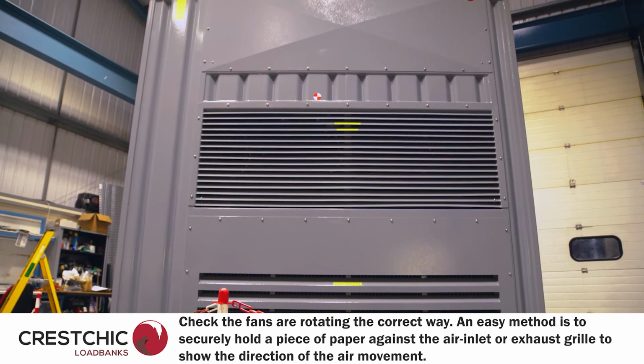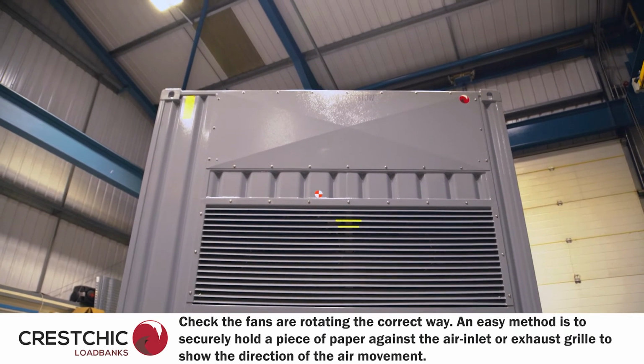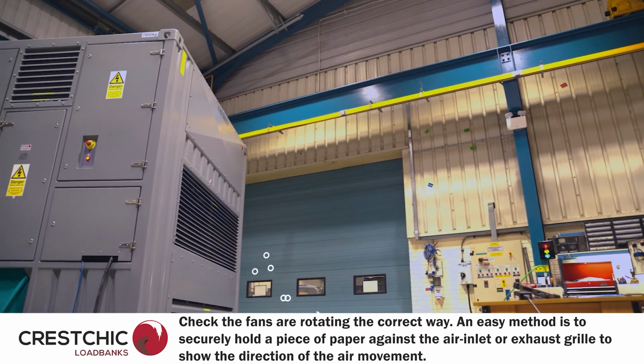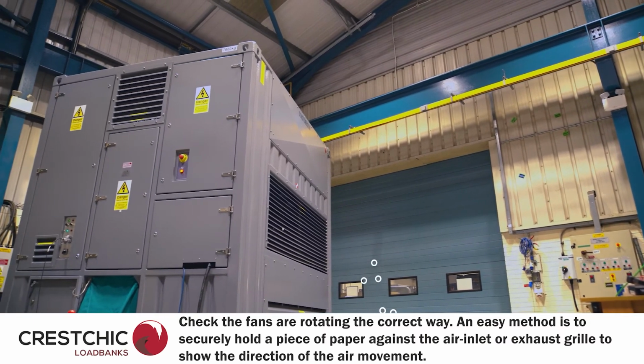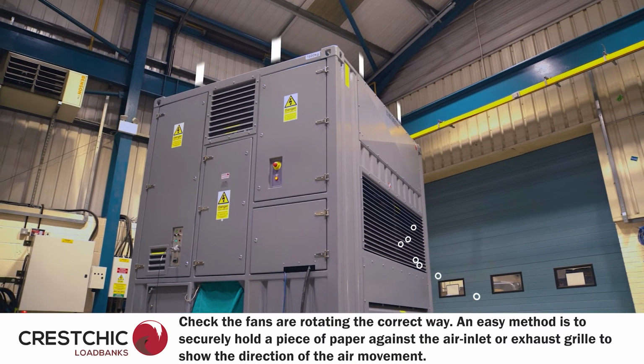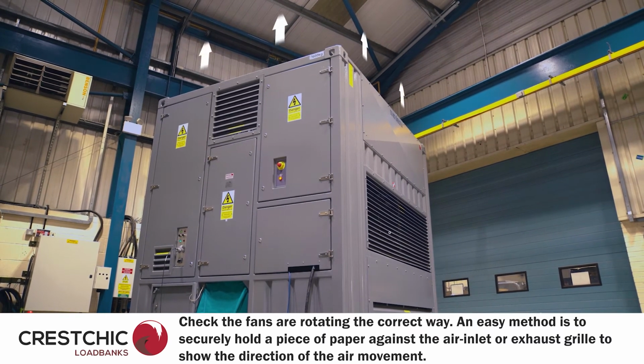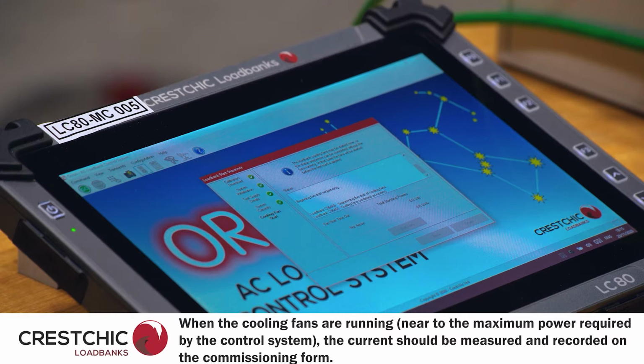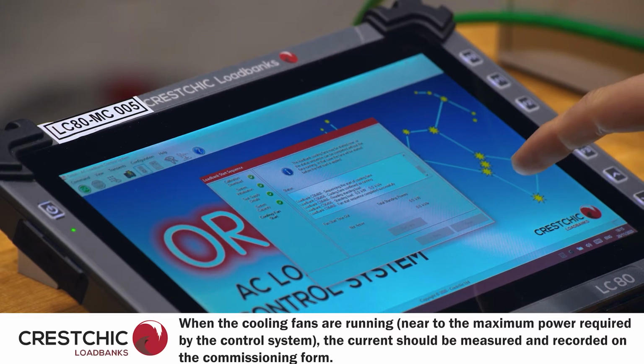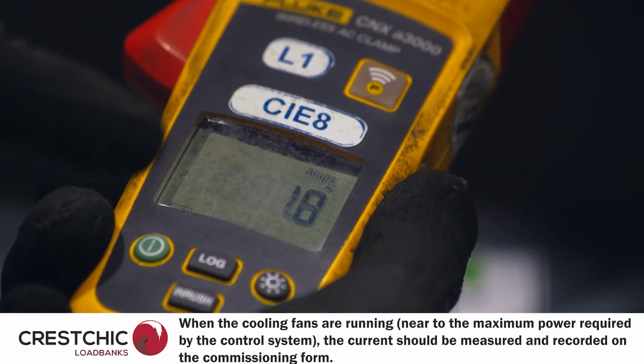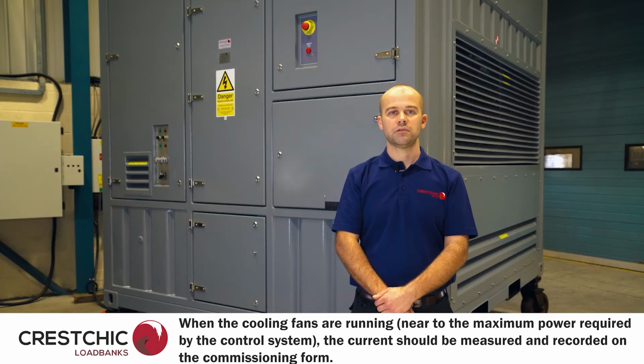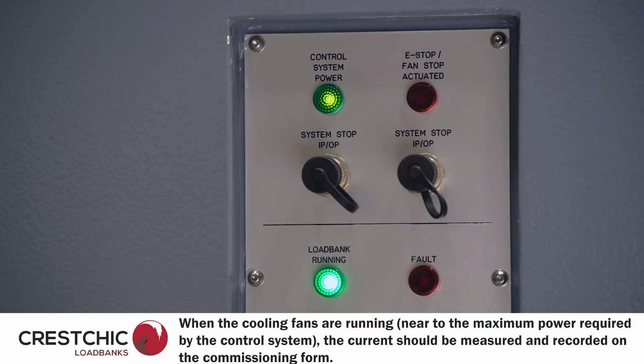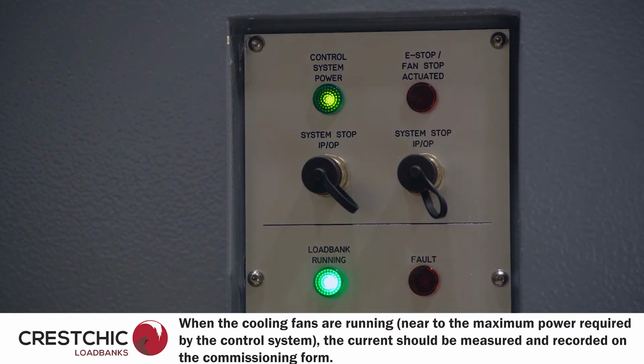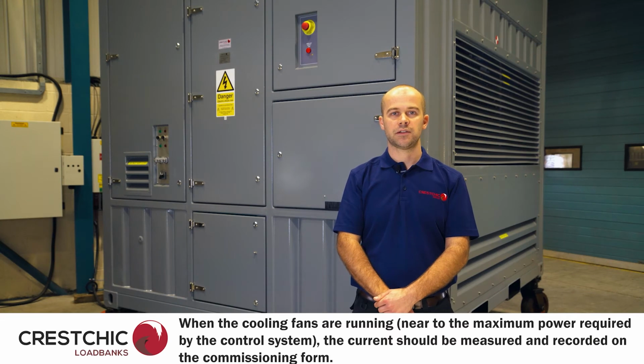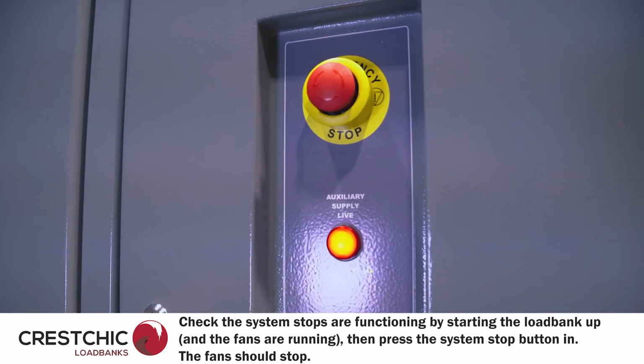The cooling fans beneath the elements or resistors blow air over the elements. Therefore, air is being sucked in through the side grills, over the elements and out the top as hot air when on load. When the cooling fans are running, this is near to the maximum power required by the control system. Therefore, the current should be measured and recorded on the commissioning form. Whilst the fans are running, the system running indicator will be on. This should be checked.